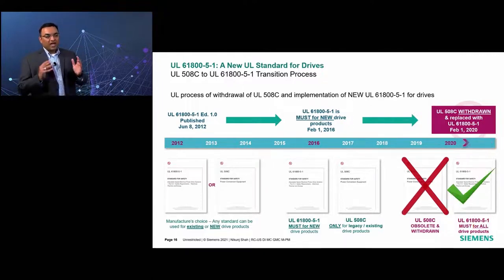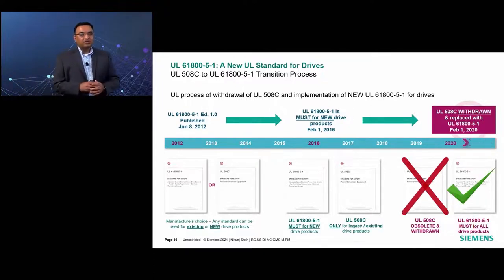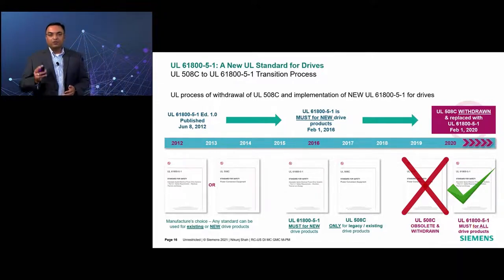In summary, after February 2020 last year, there is only one UL standard for the safety certification of low voltage adjustable speed drives, that is UL 61800-5-1. The old existing UL 508C listed drives may retain the mark moving on unless the alternate construction is made to those products. What does it mean?